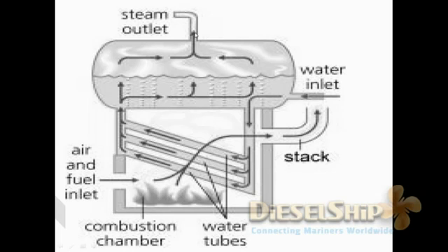Here we have the steam and water drum, where the feed water inlet is here, and here is the downcomer. Please note this point. Here is the downcomer. It's inside the boiler, so it's called an internal downcomer, and these are the generating tubes or the risers, which produce steam, and then it goes back to the steam and water drum. The steam which is formed is collected at this space, and the steam outlet is over here, and here is the burner. The exhaust gas flows through the stack.